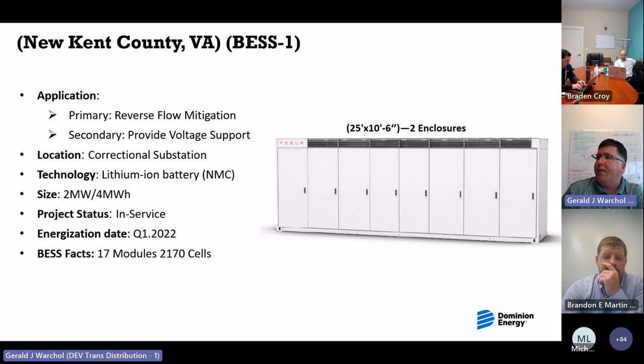This is a lithium-ion nickel manganese cobalt battery at our correctional substation. Its primary application is to fix that reverse flow problem that I showed you. Got a real good slide on that coming up. The secondary application is providing voltage support. These batteries not only charge and discharge watts, but they can supply VARs for increasing or decreasing voltage on the system. And a little fun factoid: there are 2,170 cells for each of these 2 containers. This is a pretty dense system, believe it or not, when it comes to lithium-ion. The containers themselves are 25 foot by 10 foot.